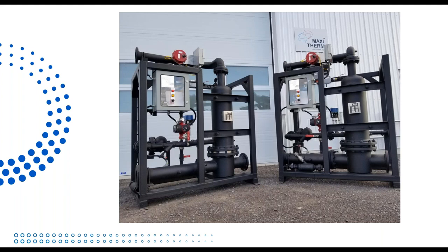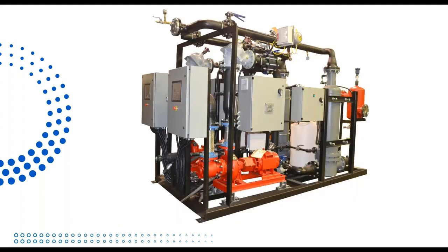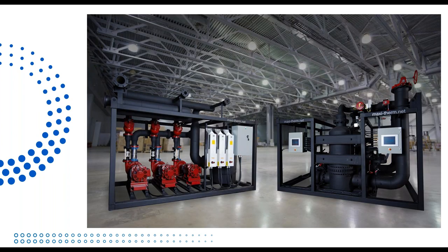So these are some pictures of work we've done in the past. We can do a complete skid package with the circulating pump for the building. This is for a glycol system. There's a tank here for the safety valve on the glycol, a 4 million BTU process. This is a 30 million BTU process, which means 900 horsepower. So imagine in your mind a 900 horsepower boiler. Well, this heat exchanger is good for 900 horsepower.